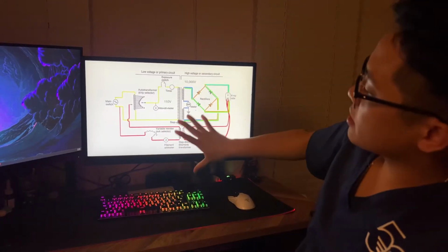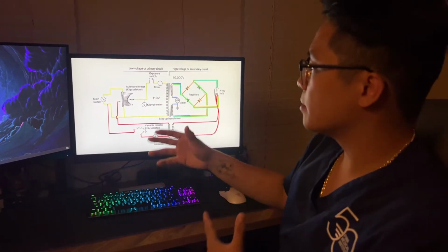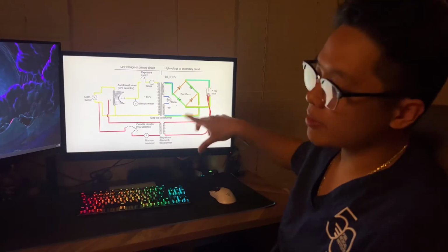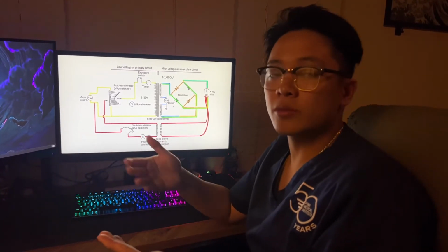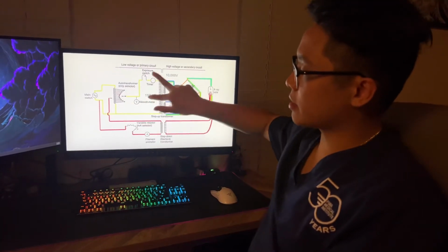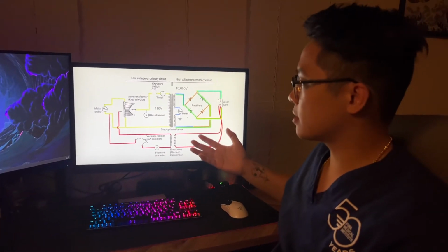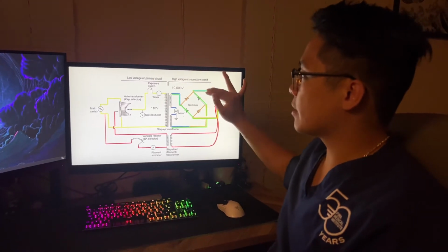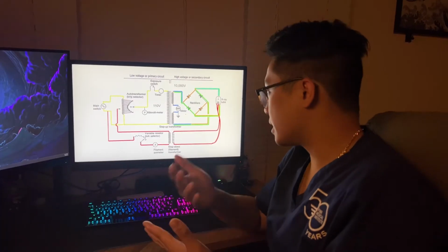While this is all happening, it seems like it's all one by one, but it must be noted that everything is happening within 1 consecutive second, because electricity moves that fast. So everything on the kilovolt side is happening, and everything on the variable resistor or the milliamperage side is happening at the same time. The rectifiers and the meter making sure it's all 10,000 volts, this is all happening at the same time.